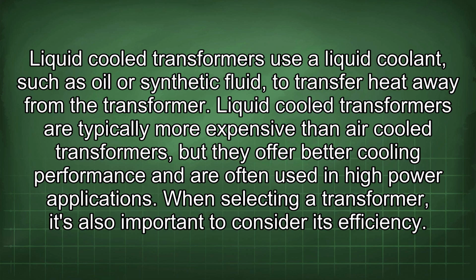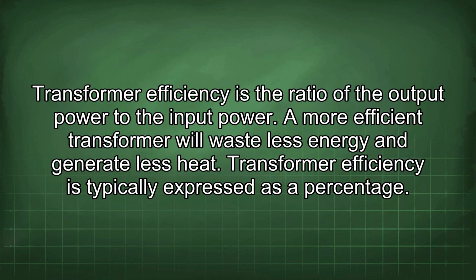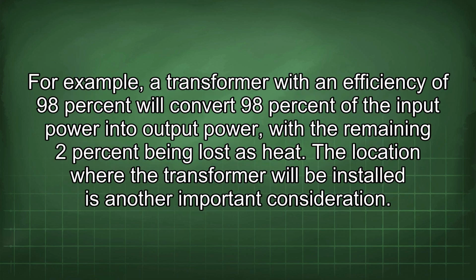When selecting a transformer, it's also important to consider its efficiency. Transformer efficiency is the ratio of the output power to the input power. A more efficient transformer will waste less energy and generate less heat. Transformer efficiency is typically expressed as a percentage. For example, a transformer with an efficiency of 98% will convert 98% of the input power into output power, with the remaining 2% being lost as heat.